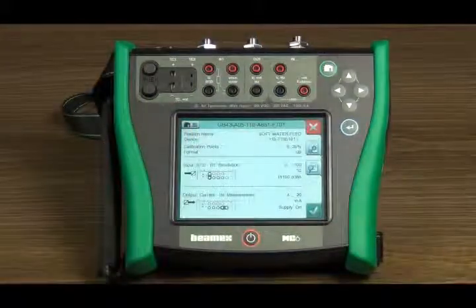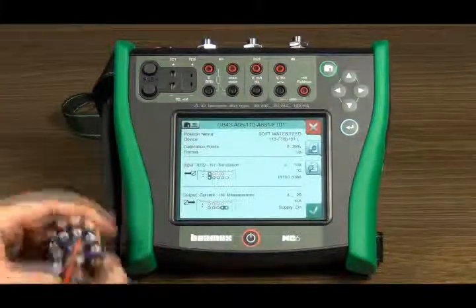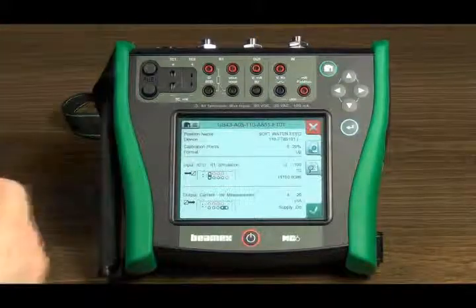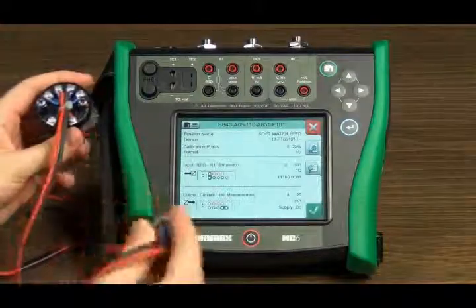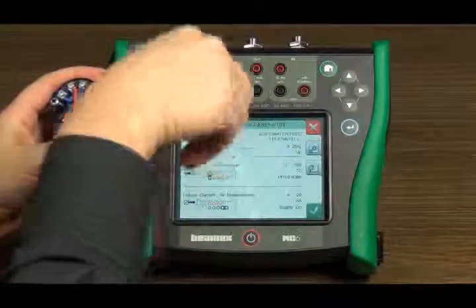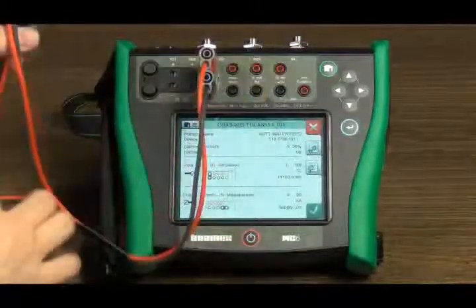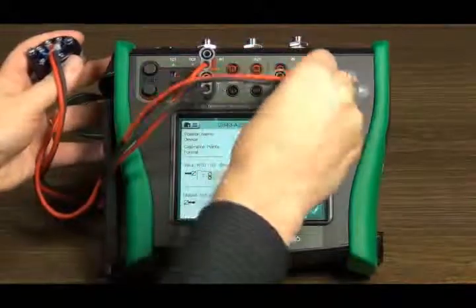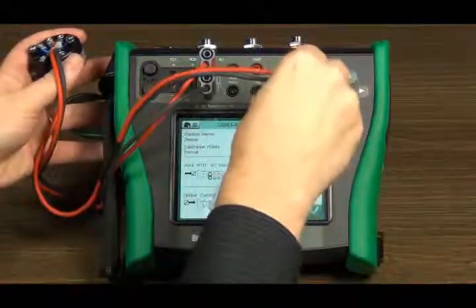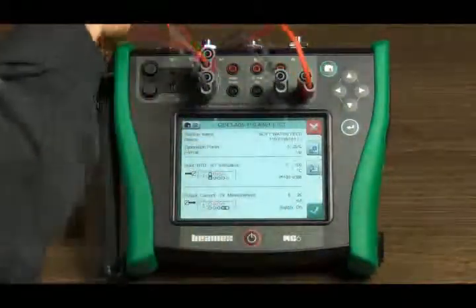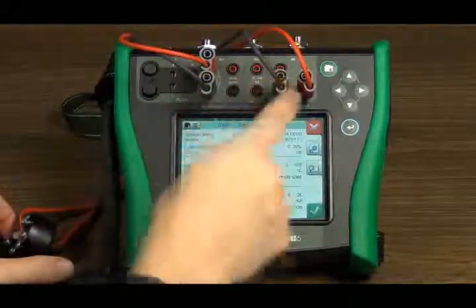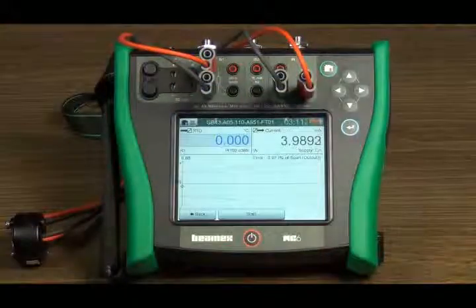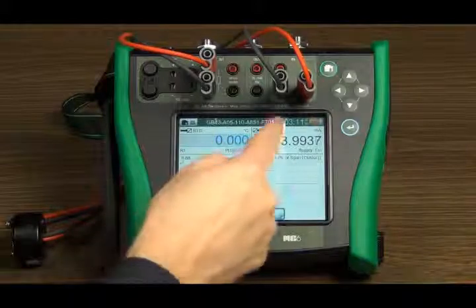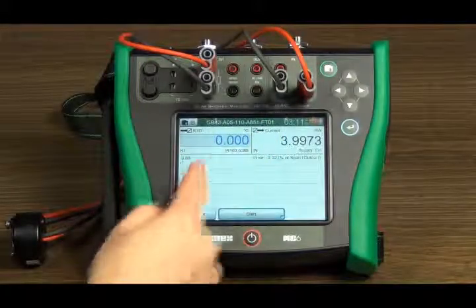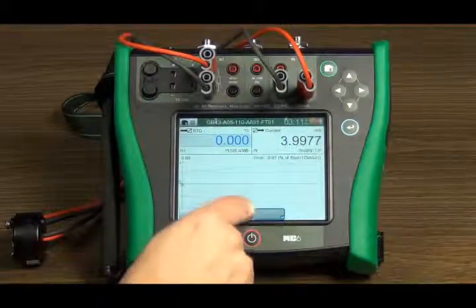Select the instrument to calibrate by tapping it. A preview page will open up showing the summary of the instrument settings. It also shows connection diagrams helping to make the connections. Once the calibration is activated, the instrument input and output will be shown at the top of the screen. The rest of the page is used to show the instrument's error graphics. To start the calibration, tap the Start button.